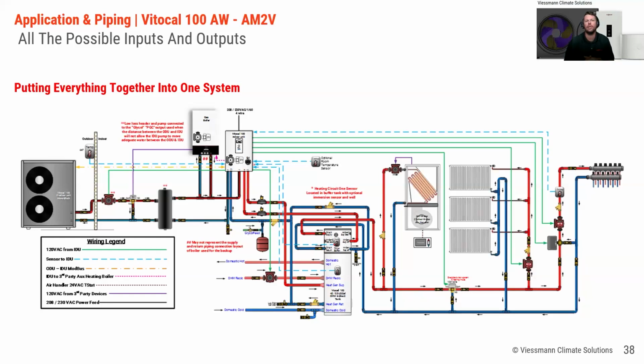The question was about that Modbus and interconnect communication wire. That is just a communication wire. The question is, does the outdoor unit get its power from the indoor unit, like we would see with a mini split? No, these are a separate 240, 208, 230 volt supply to the indoor unit and separately to the outdoor unit. With the indoor unit having those electric resistance elements, there's going to be quite an amp draw when those are engaged, so that's a separate 40 or 50 amp double pole breaker, depending on the model size. And the outdoor unit is again a separate 208, 230 volt double pole breaker, 20 to 45 amps if my memory serves, depending on the model size.